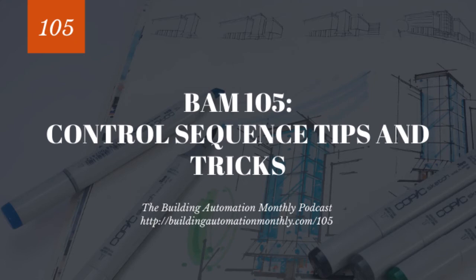And I said, okay, so what's the heat being used for? Well, I preheat the outdoor air coming in. Okay, so it's got preheat. What else? Well, it's got a cooling coil. Okay, the cooling coil's closed, so we're good there. What else? Well, it's got a reheat coil. Okay. Well, what's the discharge air coming off of that unit? Oh, it's 60 degrees. Okay. Are the other spaces all cooled down, or are they warm? No, they're all at set point.